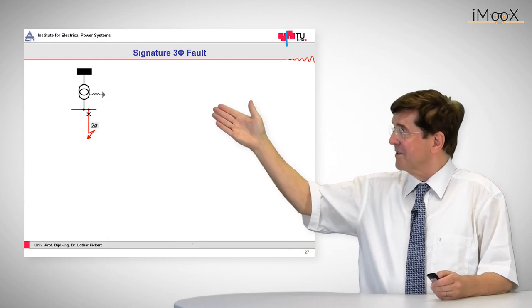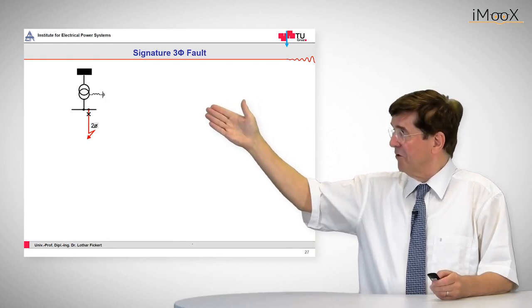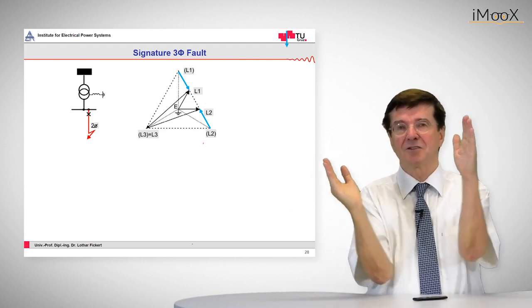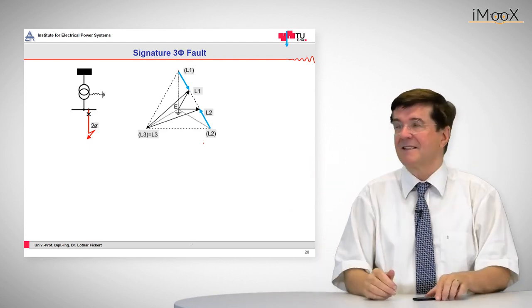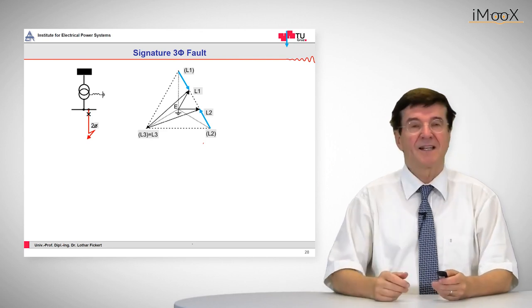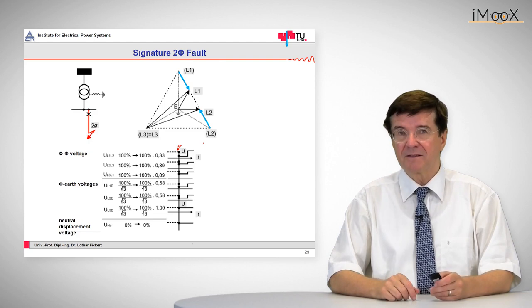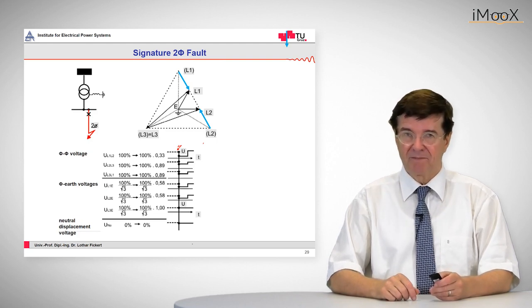Again we start with the same systematic. We start with the appearance of the fault, then with a triangle. And here we see that the triangle collapses only in two phases. The two phases in this case are L1 and L2 and the traces repeat the same pattern.